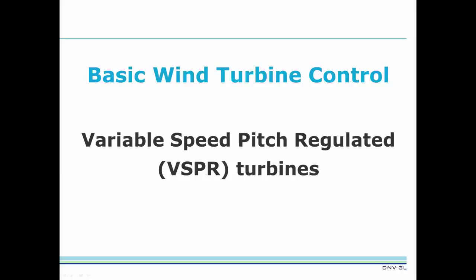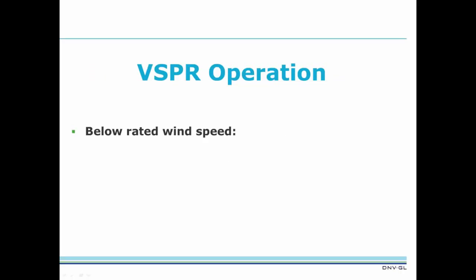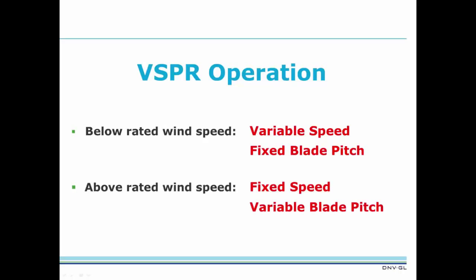Most commercial wind turbines are variable speed pitch regulated machines. This means that below their rated wind speed, they operate at variable speed with fixed blade pitch. For wind speeds above rated, they run at fixed speed with variable blade pitch.